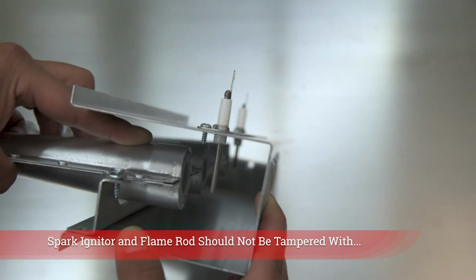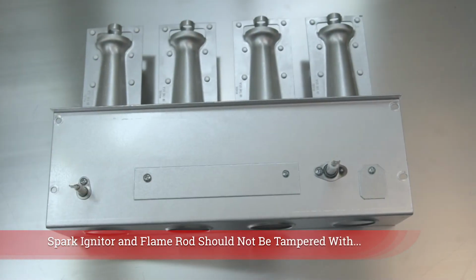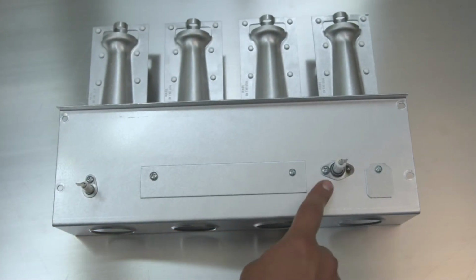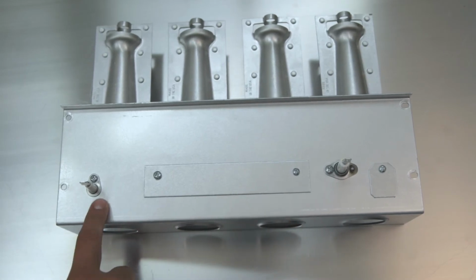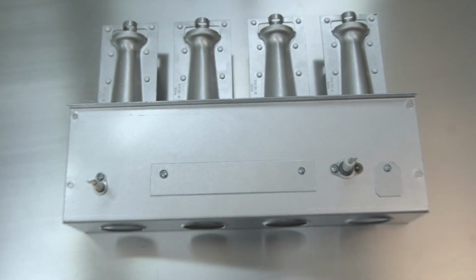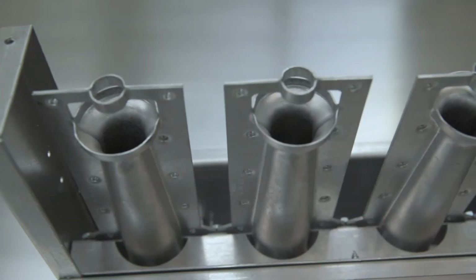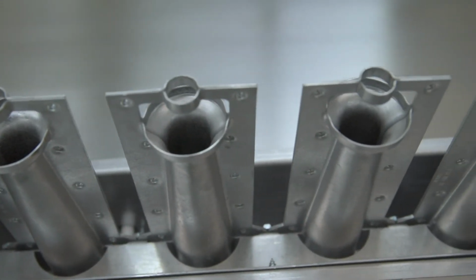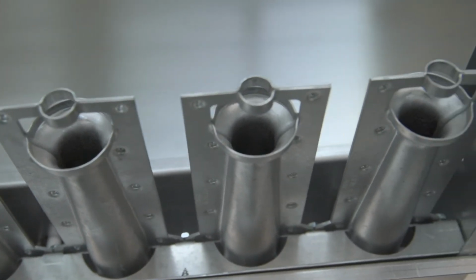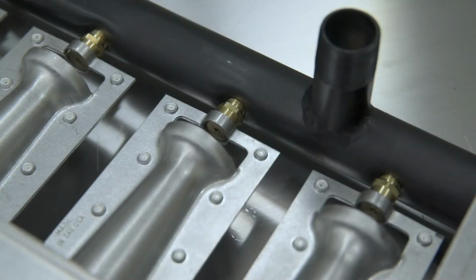The spark igniter and flame rod should not be tampered with in any instance. The spark igniter initiates the flames, and the flame rod monitors the flame during operation. The atmospheric in-shot burners are mounted in the burner tray very carefully to ensure proper alignment. In-shot burners mix the gas and combustion air to produce a flammable mixture.